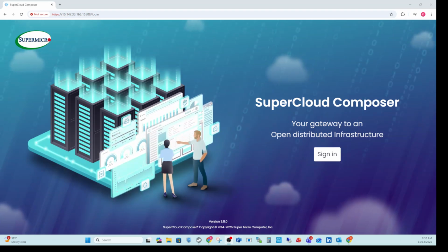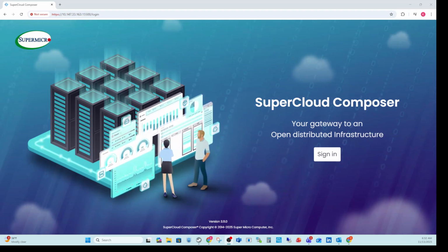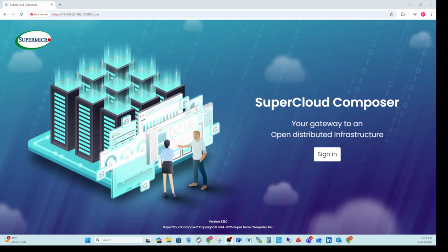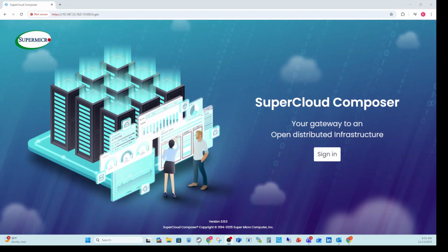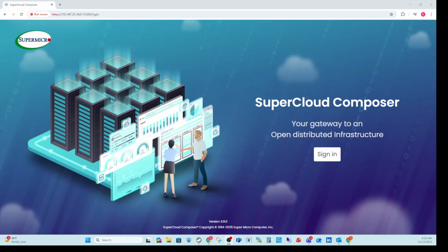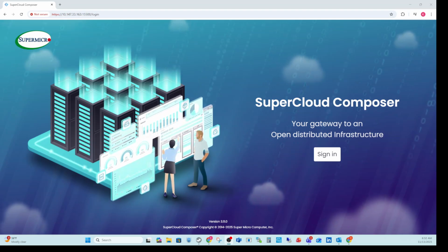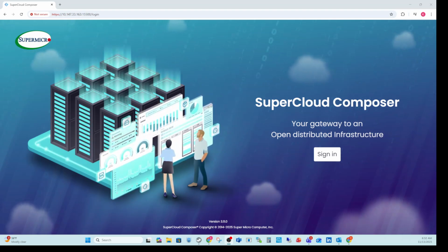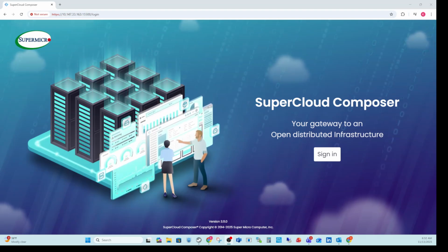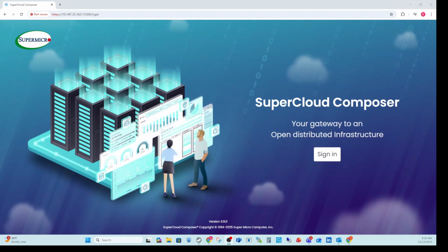And so today we're going to look at an InRow solution, which is the InRow CDU that is to support 10 racks. It's a scalable, viable option for you in your data center to support 10 racks instead of putting 10 racks with an in-rack CDU in each individual rack. So this in-row CDU is going to be associated with this concept of a group that we talked about in a previous video in the rear door exchanger. So this is another valuable option here for you in the data center.